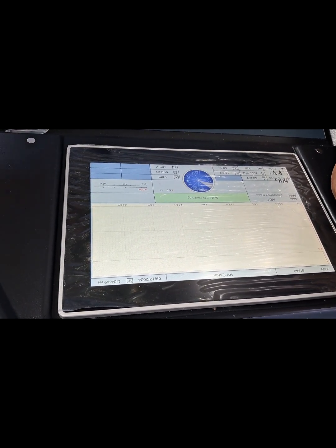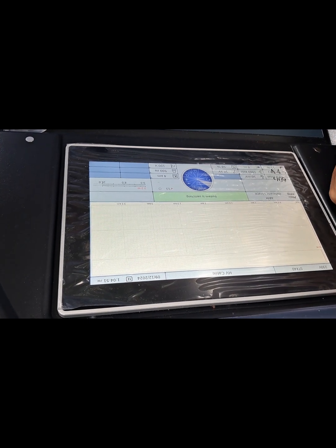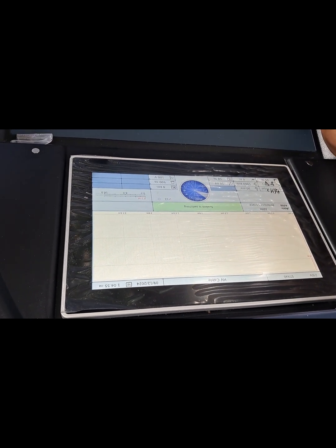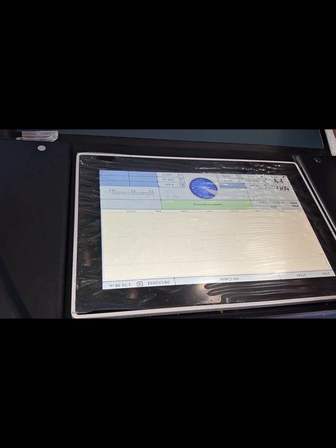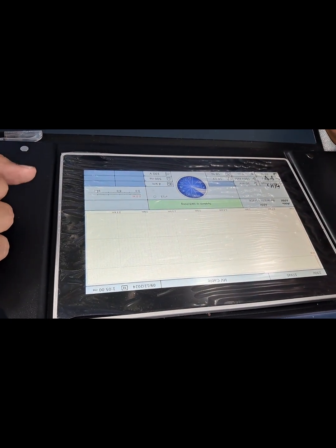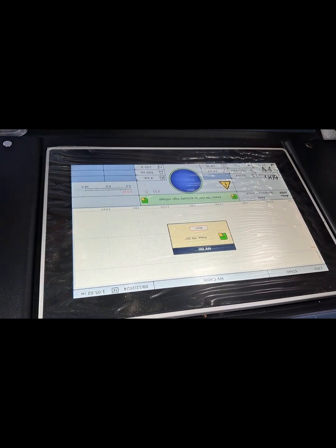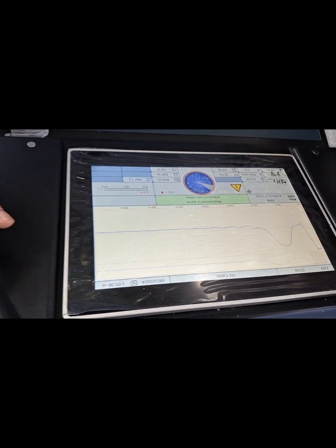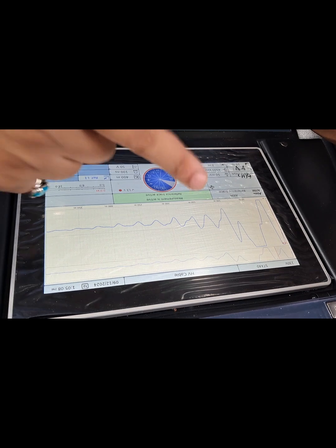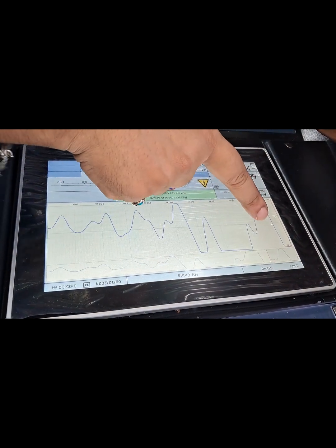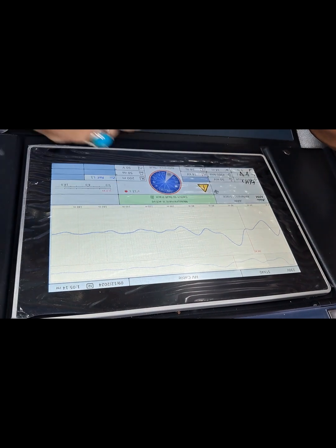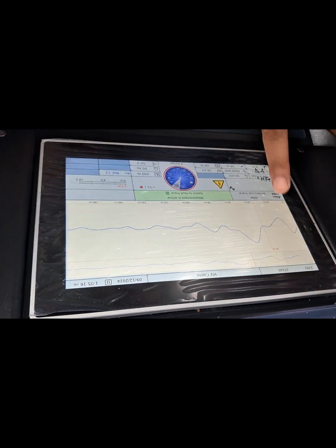System is switching. So I am seeing pre-location once. Press HV on. So, what is this? This is TDR. So in TDR, I can perform this function only. I cannot do more testing. It is showing that cable length is approx. The cable length is approx 34 meter.